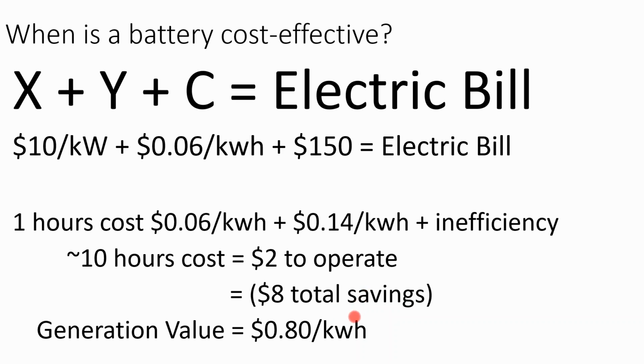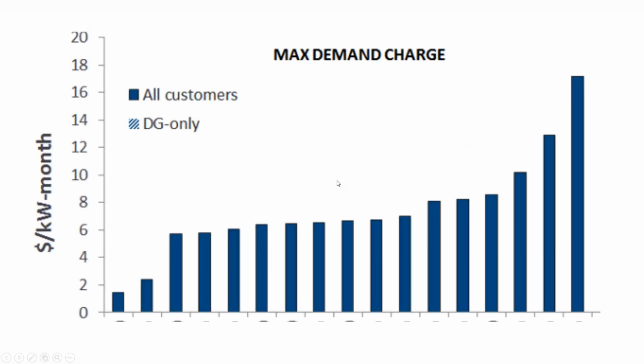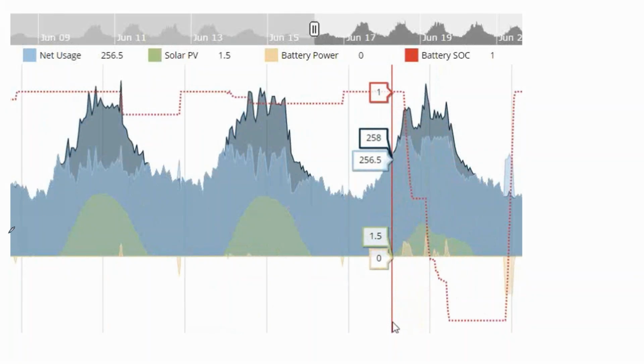So what that means is with these demand rate structures, the higher the demand goes, it's possible not to completely eliminate your electric bill, but to implement what I call a solar peaker plant, where you aren't trying to do a solar array to eliminate 100% of the area under the curve, or trying to completely eliminate a facility's energy use. All you're trying to do is run a solar array enough to charge a battery, and give your facility a haircut, chopping off the spikiest spikes of your demand curve.